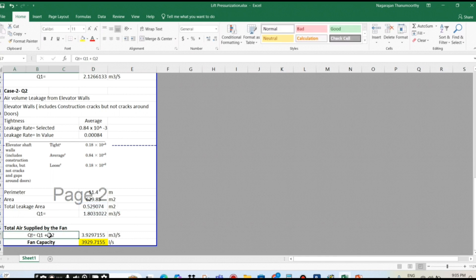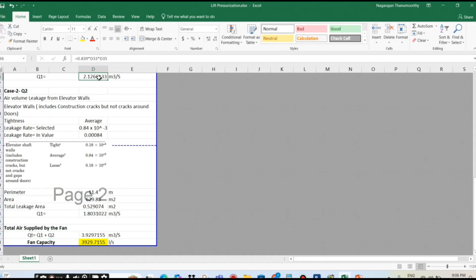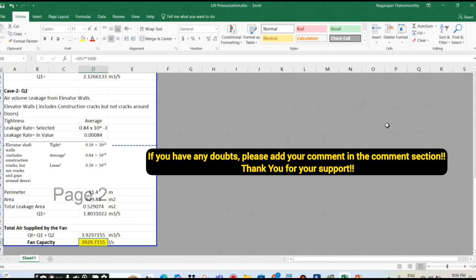So QT — the total air supplied by the fan — is equal to the leakage from the wall plus the leakage from the door frame and gap arrangement. So the total will come in cubic meters per second, and you can convert to liters per second. So this amount of air you have to supply from the top of the lift for the pressurization.